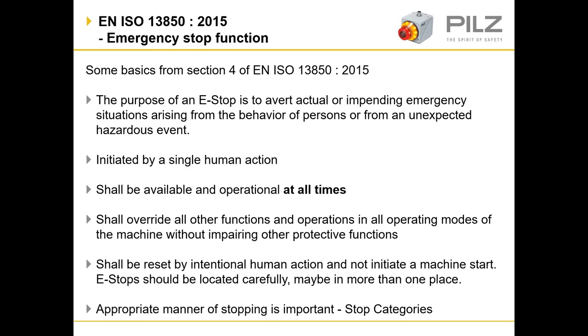Emergency stops shall override all functions and operations in all operating modes of the machine without impairing other protective functions. For example, guard switches may be bypassed to allow for slow speed, machine jogging or setup, but the e-stop must always be operational and available to override all other functions.